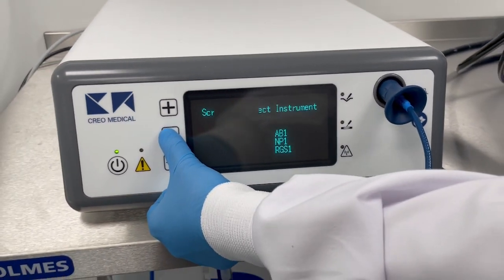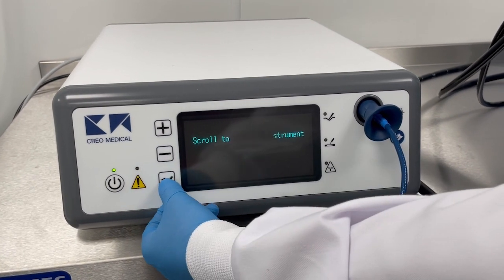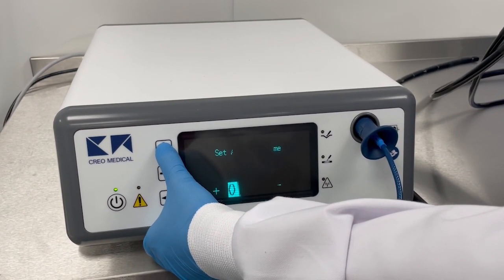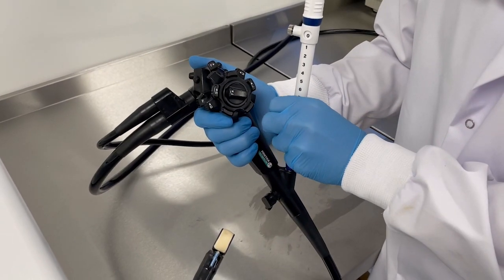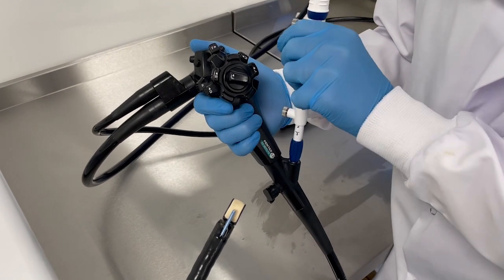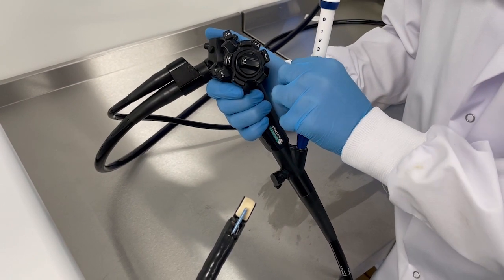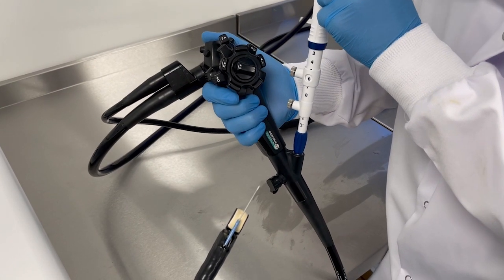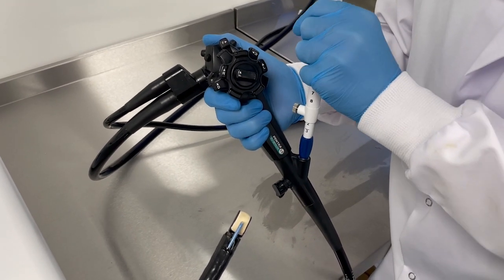Select NP1 on the generator interface and confirm the selection. Select the desired ablation time using the plus and minus buttons and confirm the ablation duration time. The handpiece is now ready to ablate. Loosen the locking knob for catheter length adjustment; the catheter length is adjusted using the distance slider. Tighten the locking knob to lock the catheter length. Loosen the locking knob for needle actuation; needle actuation is done using the proximal slider. Tighten the locking knob to the desired length.